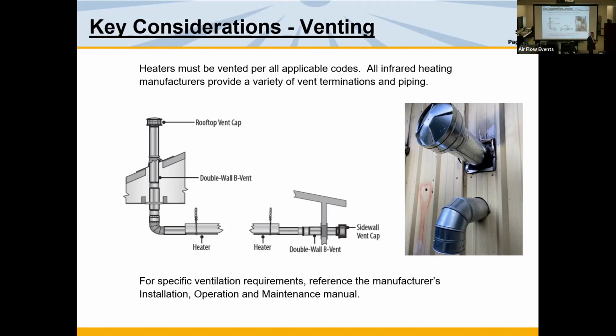Rubber up against 400 degree vent pipe resulted in that happening. So this is the third time I've been to an incident due to improper venting. If you're going through a combustible wall, if you're by a 2x4, if you're going through insulation that could potentially harness the heat energy, you've got to make sure you create spacers.